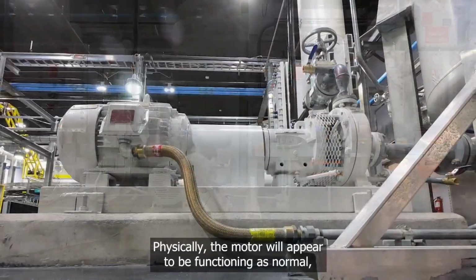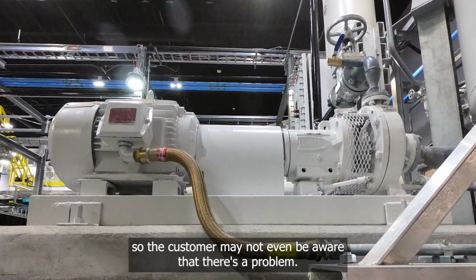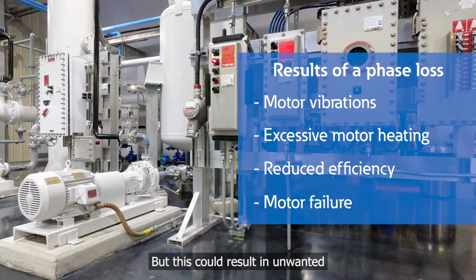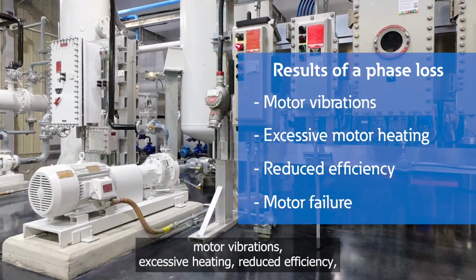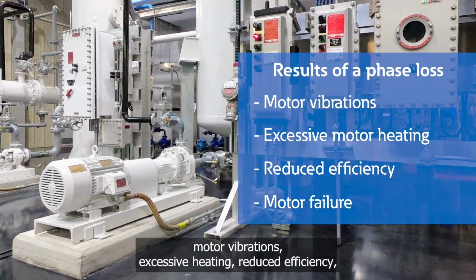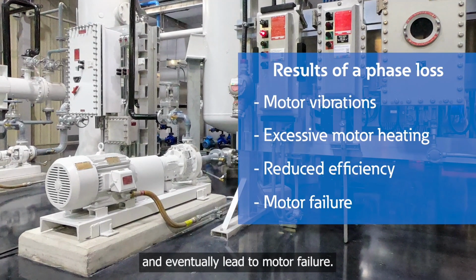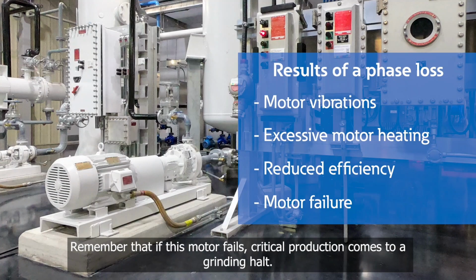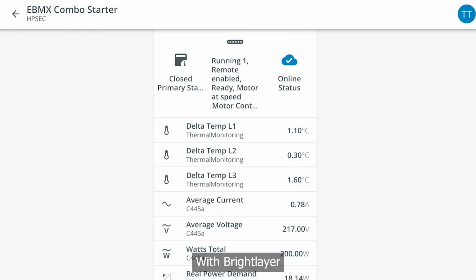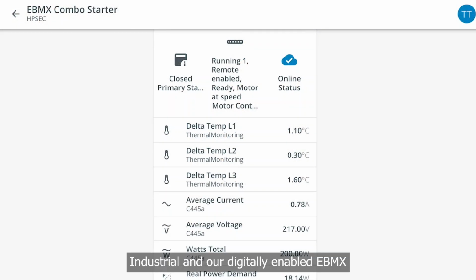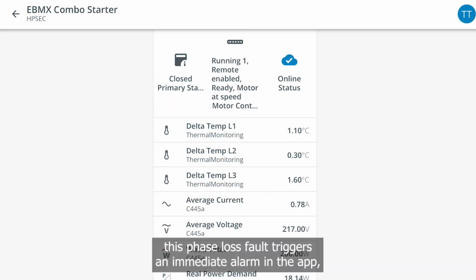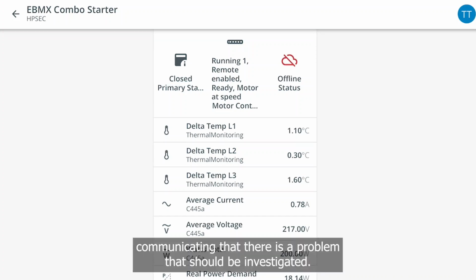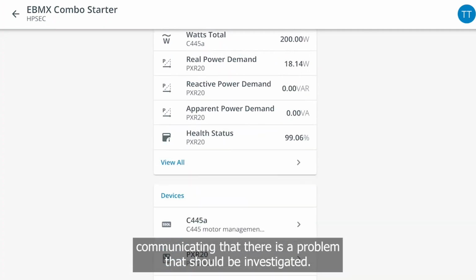Physically, the motor will appear to be functioning as normal, so the customer may not even be aware that there's a problem. But this could result in unwanted motor vibrations, excessive heating, reduced efficiency, and eventually lead to motor failure. Remember that if this motor fails, critical production comes to a grinding halt. With Brightlayer Industrial and our digitally enabled EBMX, this phase loss fault triggers an immediate alarm in the app, communicating that there is a problem that should be investigated.